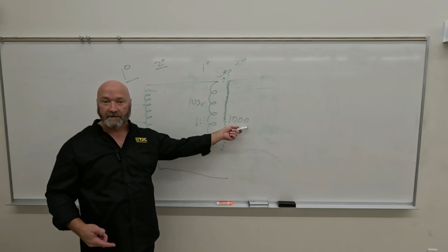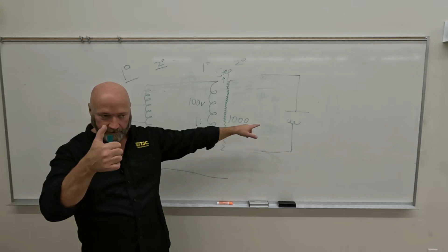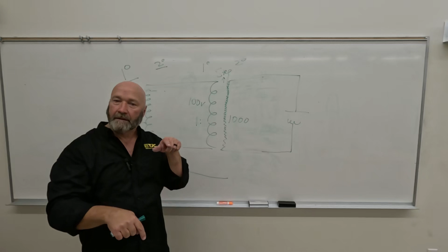Kilovoltage selector, that's where we create it over here, because we use alternating current to create a changing magnetic field so that we can increase or decrease our voltage and feed our step-up transformer whatever voltage we have selected. Now we're going to create kilovoltage so that we can go into the X-ray tube with very high voltage once we hit exposure and create X-rays, right? This portion of the circuit is not activated until you press the exposure portion of the button, if it's a 2-position button. Or if you're using the 2 buttons, you push prep, you get all this, and you get all this lower circuit that we're going to talk about here in a second. But this isn't doing anything yet. Okay? One other thing I got to add over here in a minute.